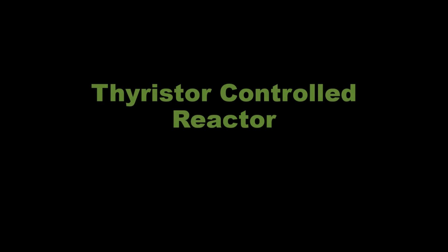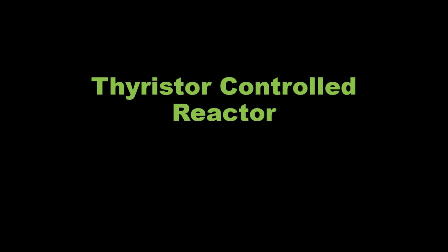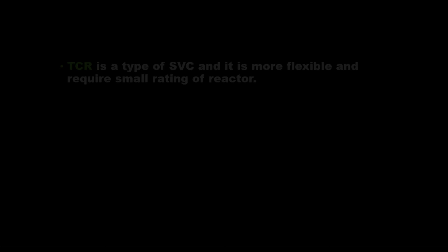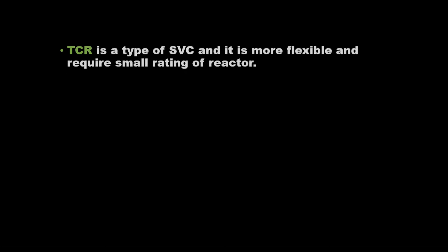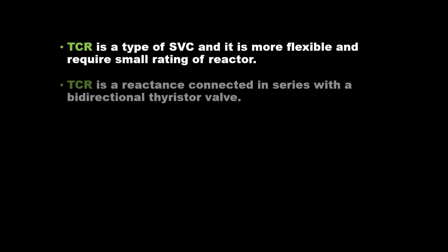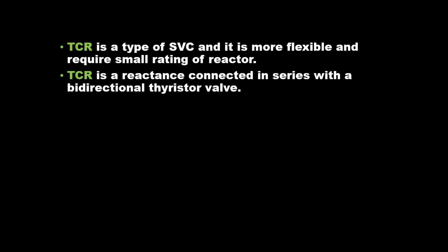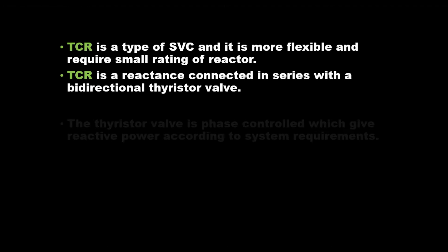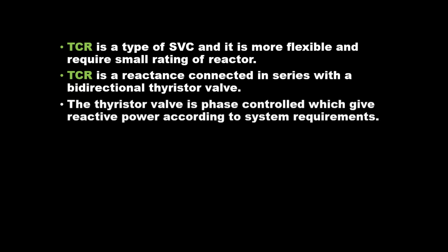Thyristor-controlled reactor. TCR is a type of SVC and it is more flexible and requires a small rating of reactor. TCR is a reactance connected in series with a bidirectional thyristor valve. The thyristor valve is phase controlled, which gives reactive power according to system requirements.